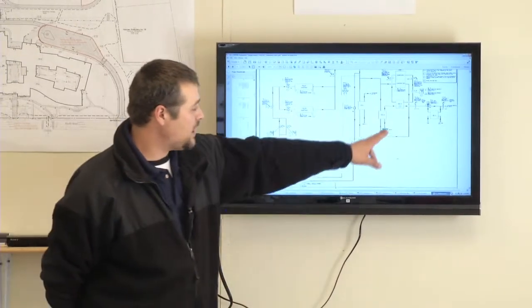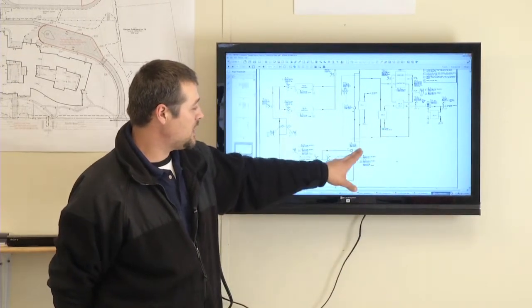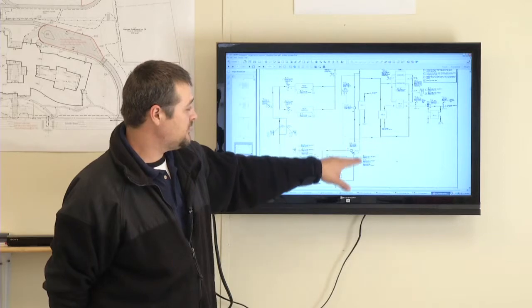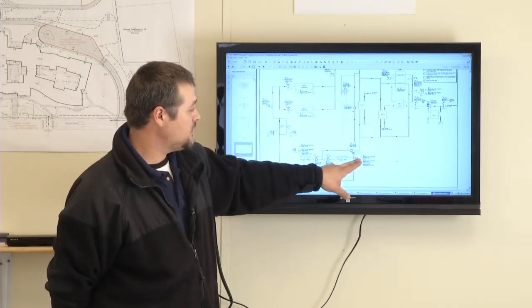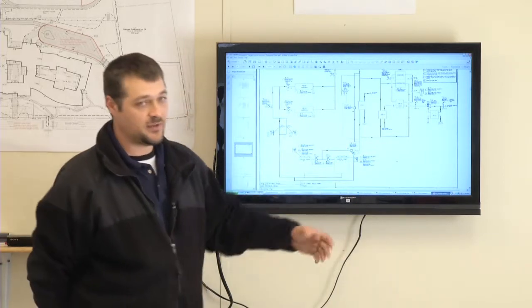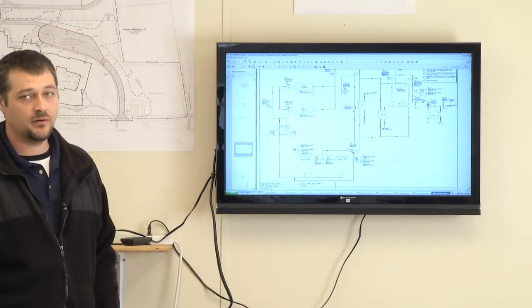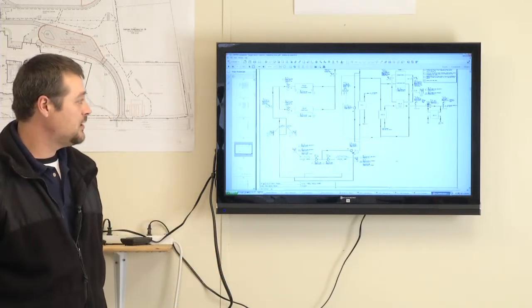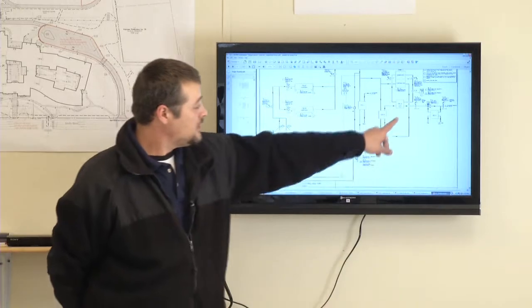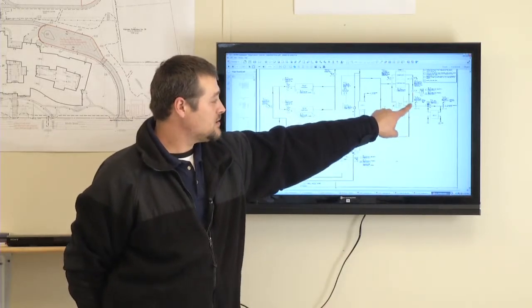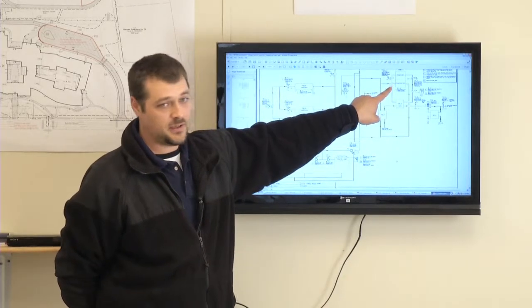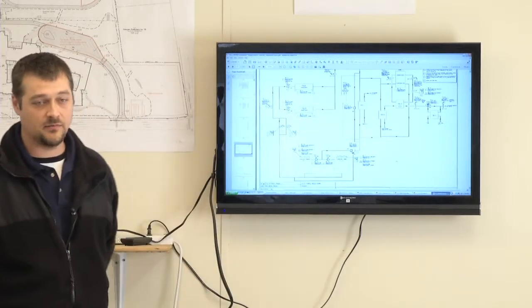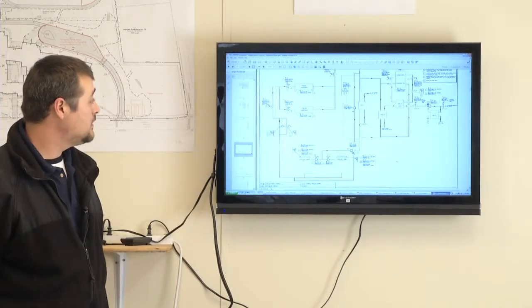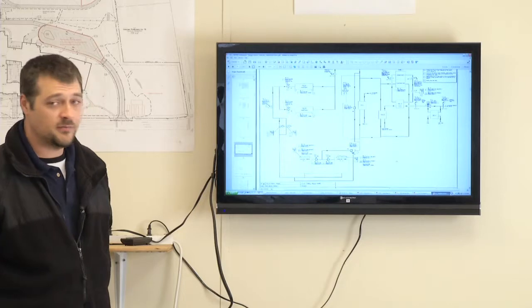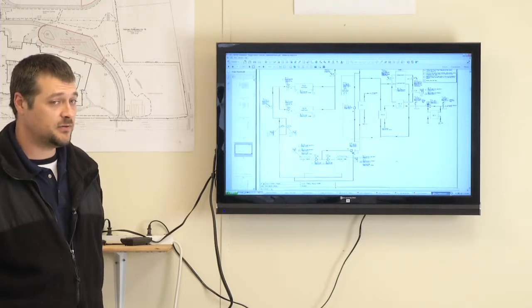There is no backup for pump 10 or pump 9 that's flowing through heat exchanger 1. So if they do fail, you will have a failure on your heat recovery machine. In that case, you would see both a red text or red box around pump 10, and you would also likely get alarms off the heat recovery device. The heat recovery machine is not necessary for the chillers to run.